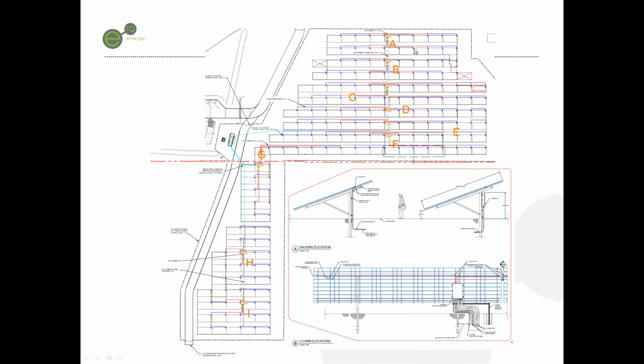And you can see here how they're all coming back into the various vComs throughout the array. We can see in here that we have 9 vComs running. This is a little bit more than we would have had to do for a standard solution. If we were doing a standard 1 megawatt block, you probably would have done it with just 4 vCom units. But because we had a pretty wide dispersion in this array, we did it with more in order to have less current coming back from each one of those vCom boxes through the distance it had to run to get back to that inverter.